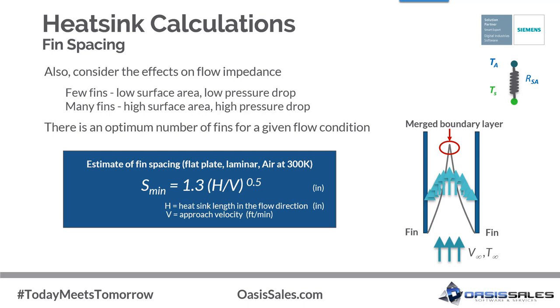One starting point is the assumption that flow in the fin channel is developing and isn't fully developed until it reaches the channel exit. When flow enters the channel, a boundary layer begins to develop on each plate. The flow is fully developed when boundary layers from each plate merge. As flow develops, the fin has maximum heat transfer rate per unit length but also the highest pressure drop per unit length. An equation is provided to estimate fin spacing given fin length in the flow direction and approach velocity. With this value and fin length, you can estimate the required fin height or number of fins as a starting point.